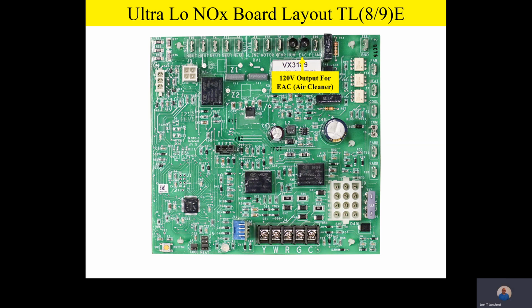The next terminal is an EAC terminal. That electronic air cleaner terminal is what EAC stands for, electronic air cleaner. It's a 120 volt output. You'll also notice there's a little black insulator on there for safety. And again, just remove that little black insulator and hook up your 120 volt output for an electronic air cleaner. Now, please make a note of this. Anytime the fan is running, this electronic air cleaner output will be energized for electronic air cleaner.